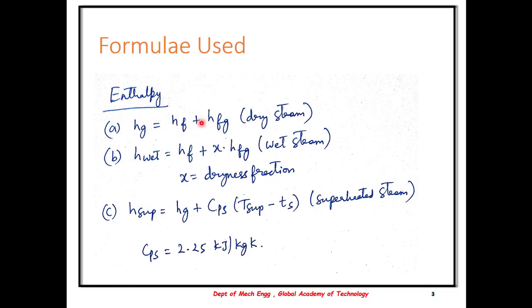Hence, you do not see X in the formula for dry steam. For superheated steam, the formula is HG plus CPS into the difference in temperatures, where CPS is the specific heat of steam, usually taken as 2.25 kJ per kg Kelvin, T superheated being the superheated steam temperature, and TS being the saturation temperature. These are the formulas for enthalpy which we are using.